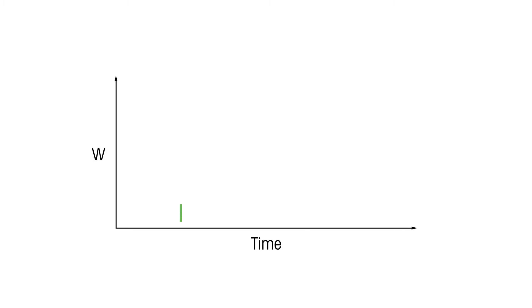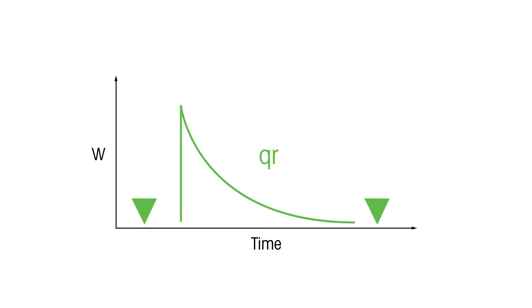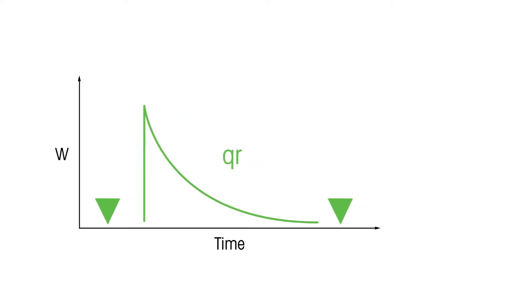Because the heat transfer coefficient and the wetted area may change in the course of the reaction, the conversion factor occasionally needs to be determined when the properties of the reaction mass are changing. This is done preferably before and after the reaction.